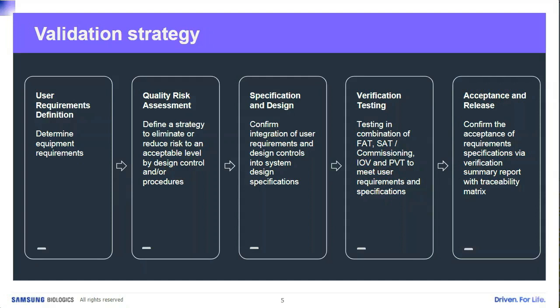Now, as we've gotten more efficient in recent years, we leverage some of that same testing. So if I was doing alarms and interlocks in the site acceptance test, there's no need to repeat those same alarms and interlocks again in the installation operational qualification.